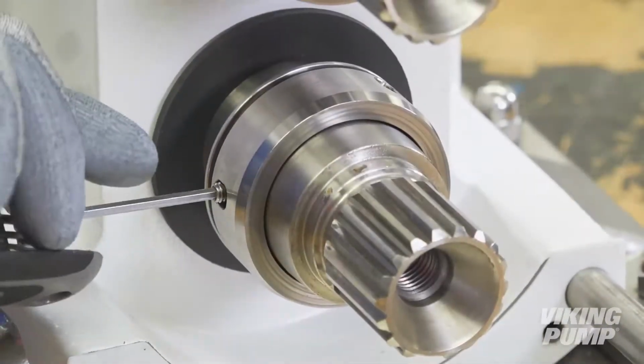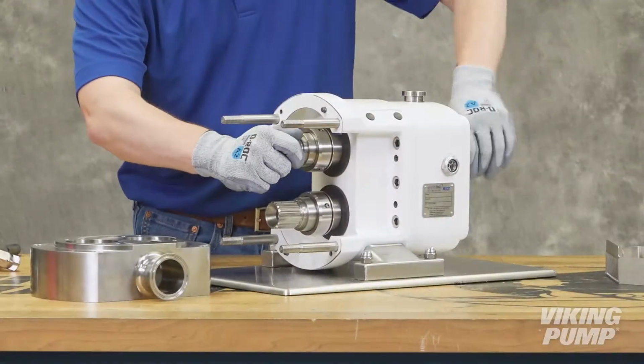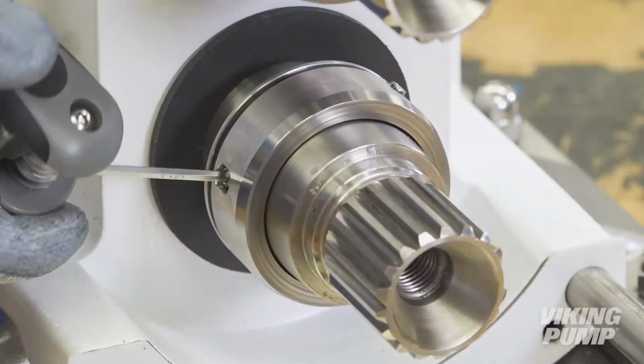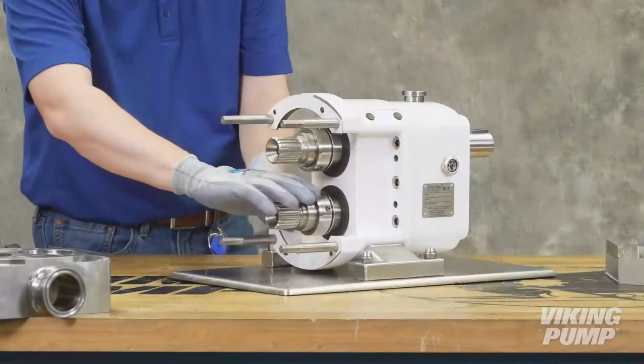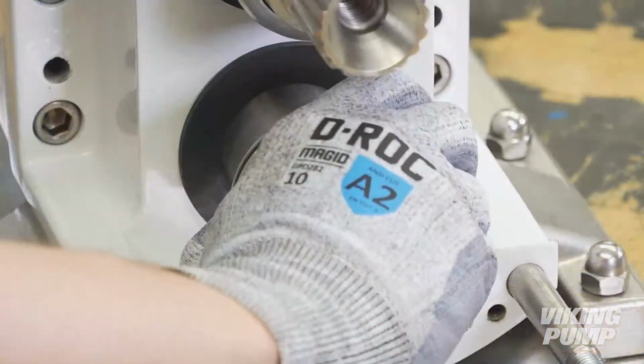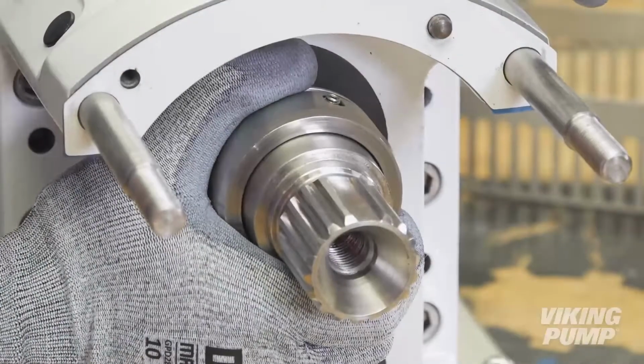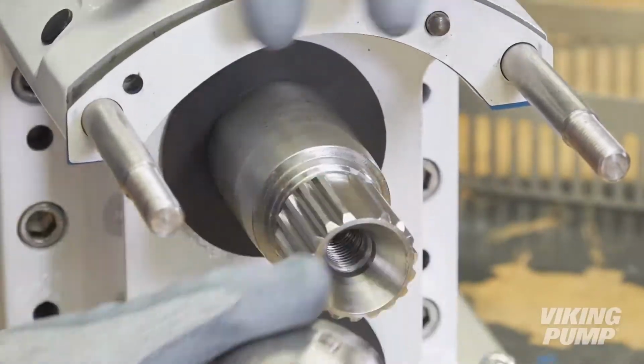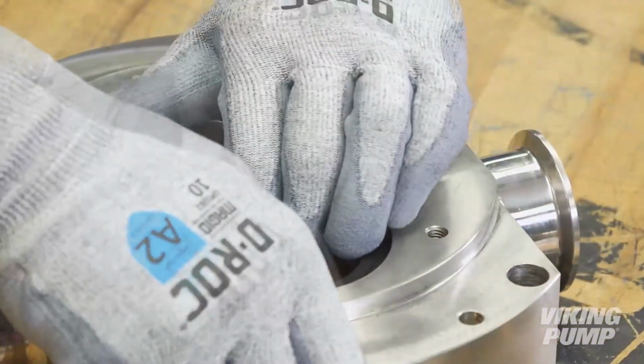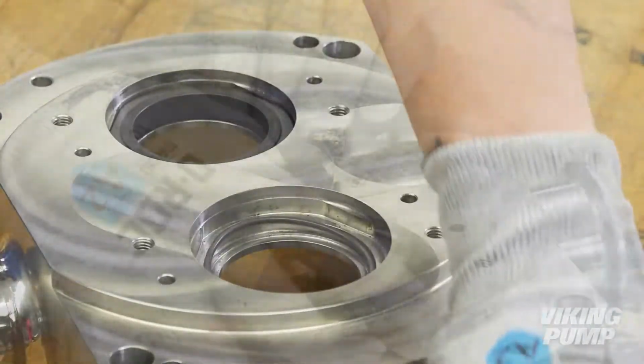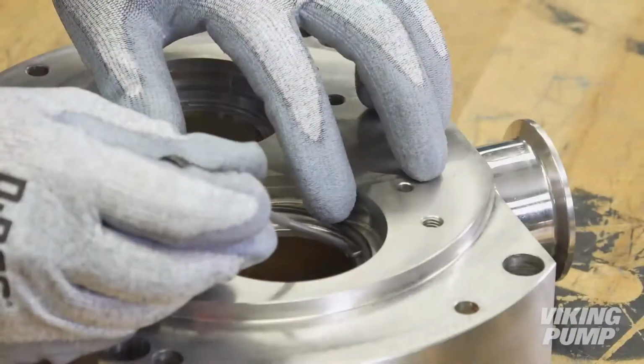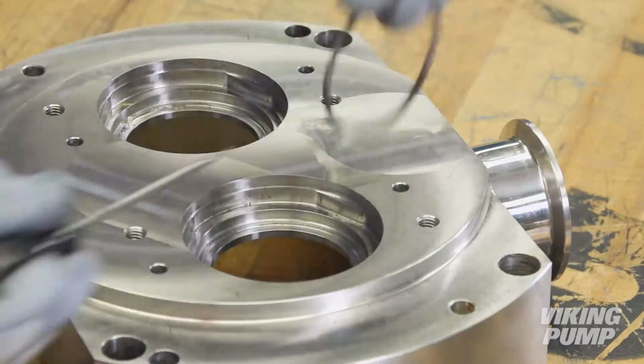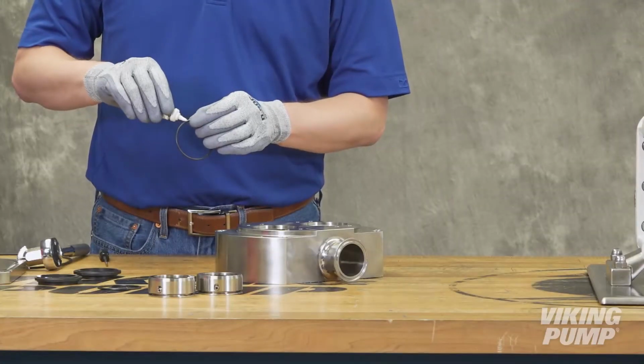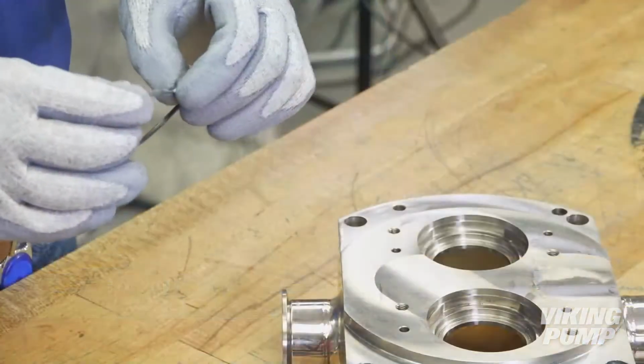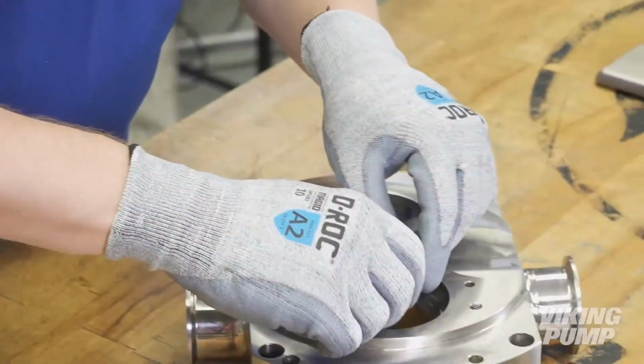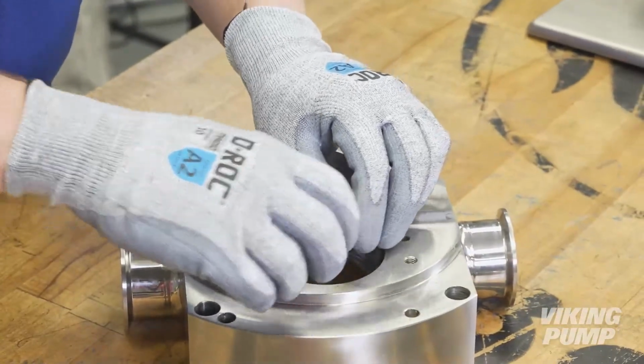For seal removal, loosen but do not remove the rotary seal set screws. Remove the seal cartridges and O-rings from each shaft. Remove the stationary seal seats and O-rings from the back of the rotor case. You are now ready to install new single mechanical seals. Lubricate and install new O-rings into the bores on the back of the rotor case.